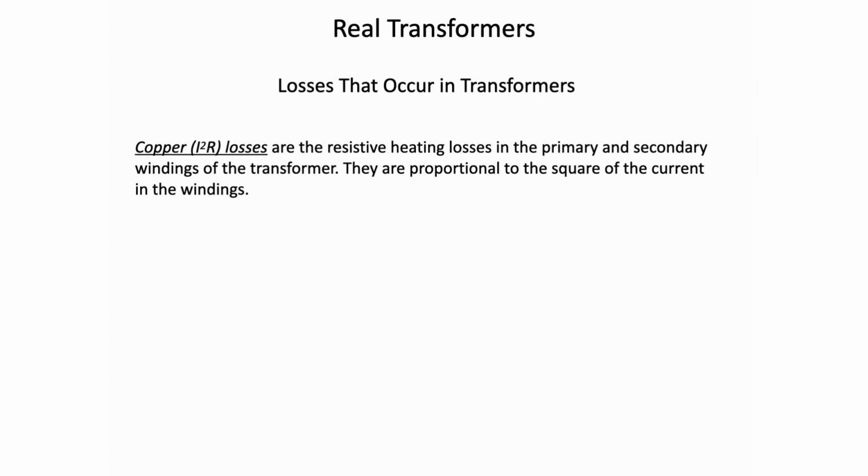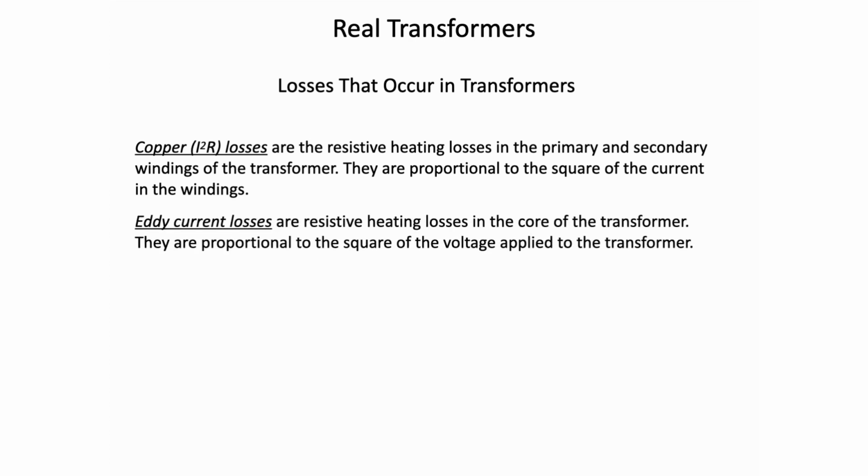Eddy current losses. Eddy current losses are resistive heating losses in the core of the transformer. They are proportional to the square of the voltage applied to the transformer.